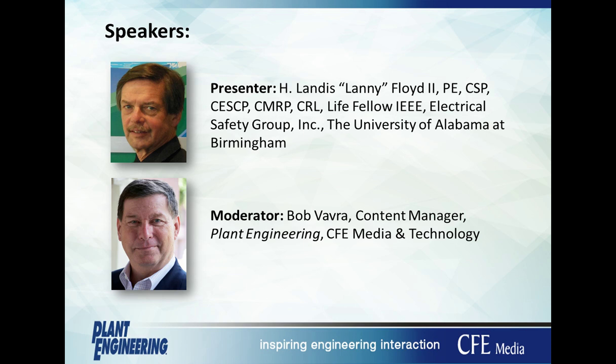Engineering design solutions, such as the metal enclosed switchgear, the double insulated tools, the GFCIs, and the touch-safe fuse block I talked about, are examples of engineering design solutions that take the risk out of the hands of the worker—they're built into the design of the equipment. So you're not depending on that worker to have to be safe all the time.